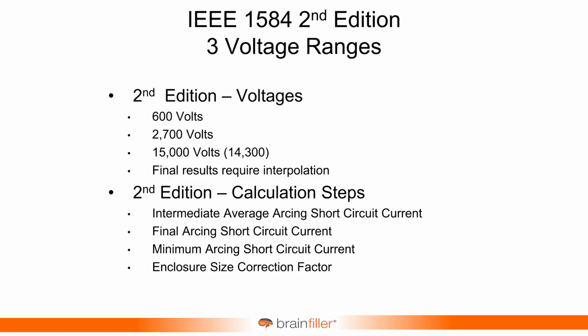But it's a little more robust, and it covers the entire spectrum. And then we also have an adjustment for the enclosure sizes. I'm going to show you there are many more enclosure sizes this time around. But if you want to fine tune it even further, there are factors that you can develop, that you can calculate, where you can further make adjustments for the size of the enclosure based on specific conditions.